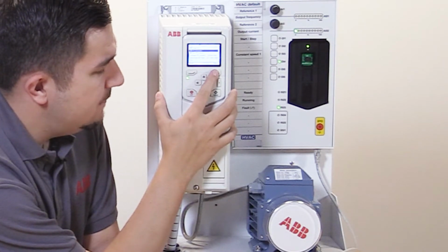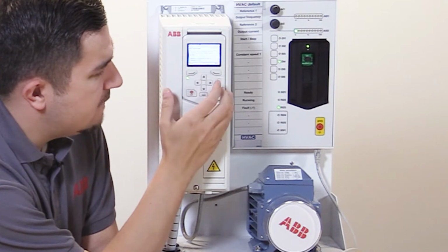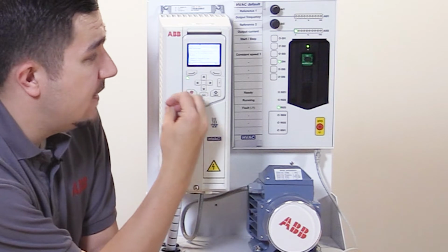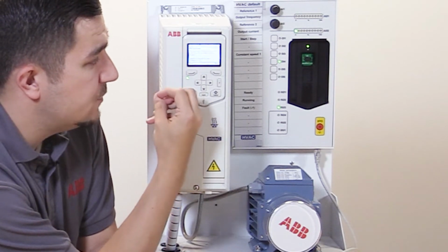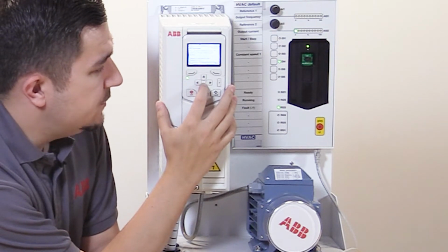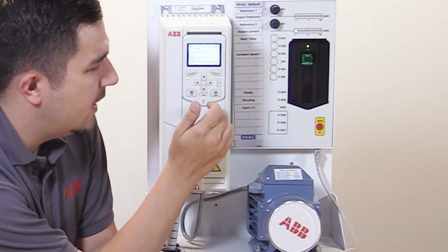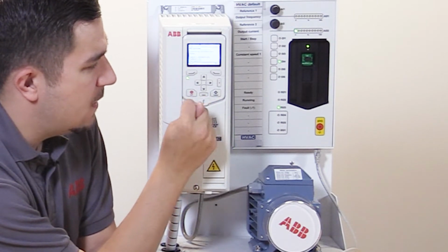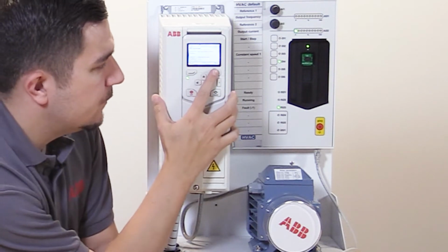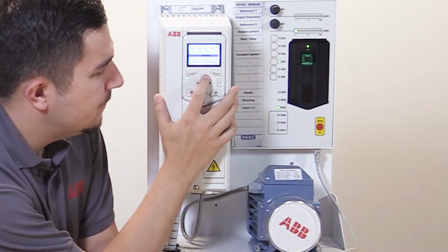So by selecting it, using the select button, we then have a very step-by-step process where the assistant will configure a very simple PID control using the secondary control location. When we use this setup, it has typical settings where our feedback is coming from our analog input 2, and the start and stop will come from our digital input 1. Once we're happy by reading through that, we click on to next.